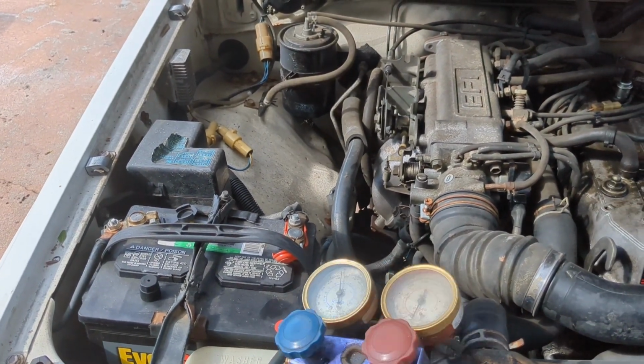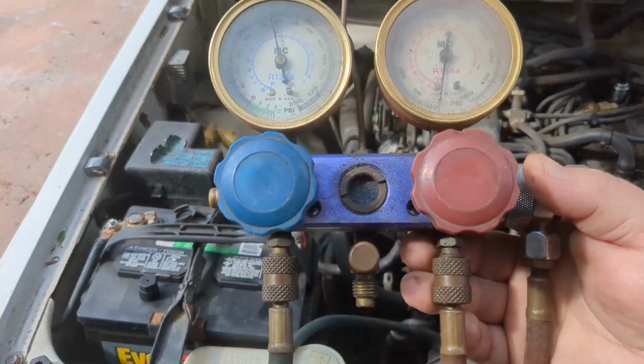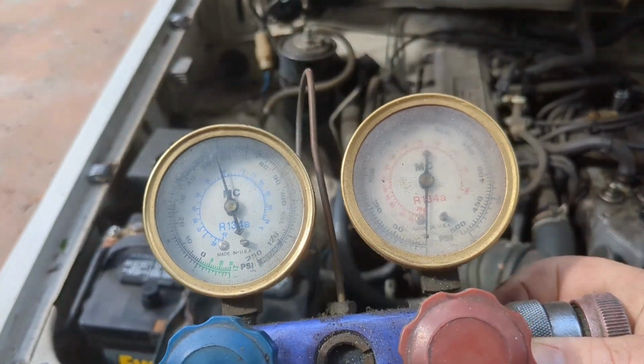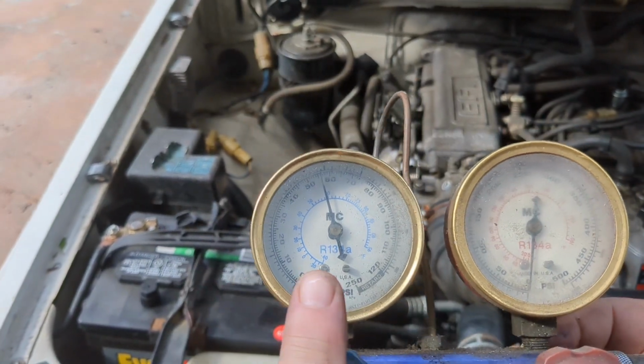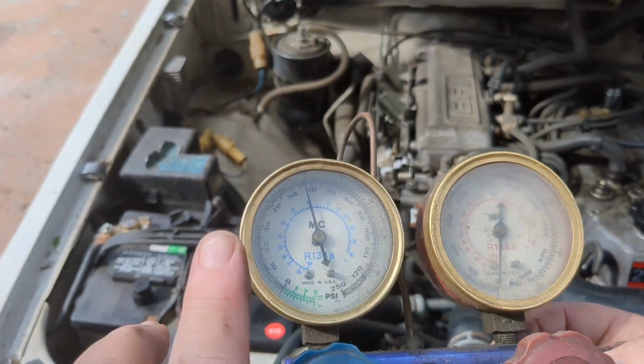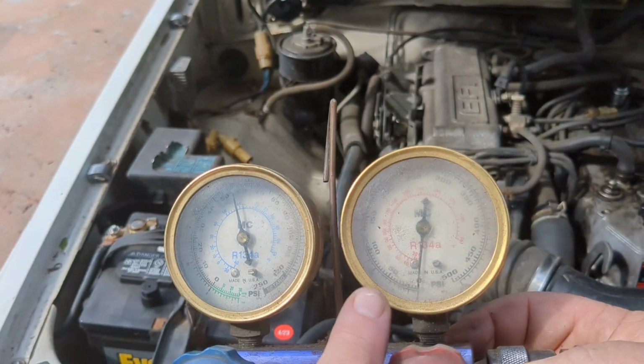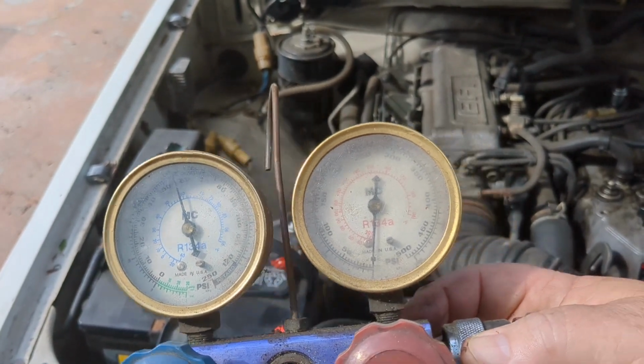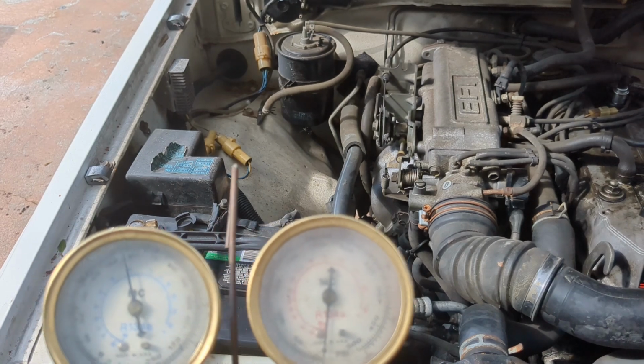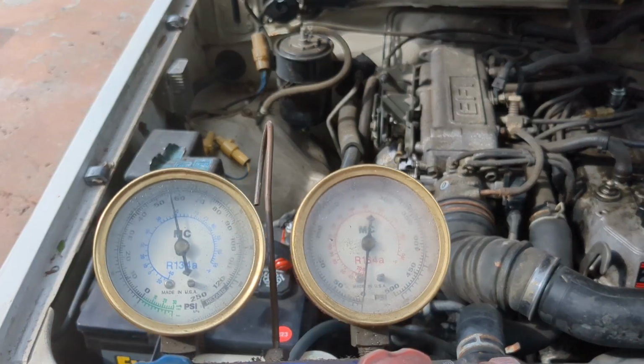Normally you'd hook up the high side and the low side, but I don't have the correct fitting for the high side. You can see we're running about 55, which is way too high. The high side's probably pushing 300 because this line down here is blistering hot.